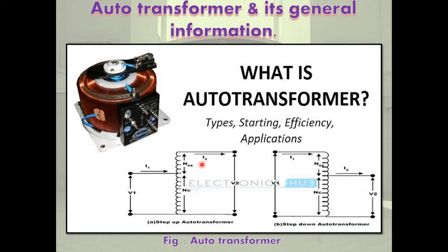Auto transformer rating is two winding transformer rating into 1 upon 1 minus 1 upon R, where R means ratio of high voltage to low voltage of transformer.